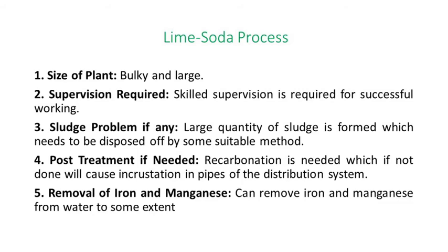Next, the result obtained. The lime soda process removes the maximum hardness but not less than about 50 mg per liter, and the zeolite process removes all hardness from the water, that is, the zeolite process obtains water of zero hardness. Okay. Next, removal of color due to iron and manganese. The lime soda process can remove the color. Okay, and the zeolite process can also remove the color due to iron and manganese, but that is going to be costly.